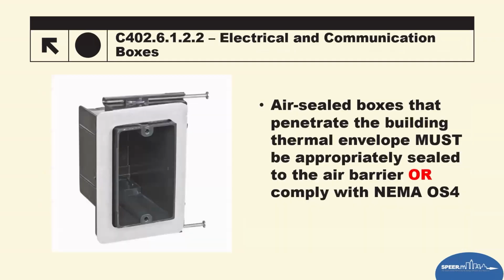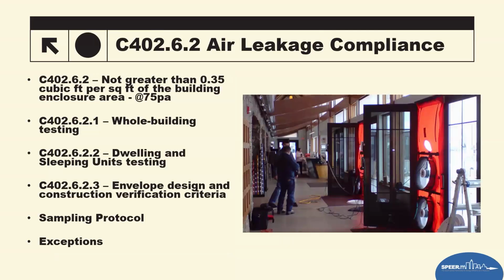Air sealed boxes, same thing as residential. If you use air sealed boxes that are manufactured to be airtight, then it needs to follow a NEMA OS4. If not, they need to be air sealed to the envelope itself. So whatever means that you have to do, either putty packs or poly seal or fire caulk or gaskets or a combination of all the above, you've got options to do one or the other. They made it clearer in the 2024 than it has been previously, but these things need to be done when it penetrates the envelope itself.